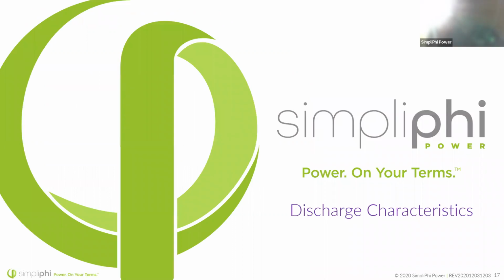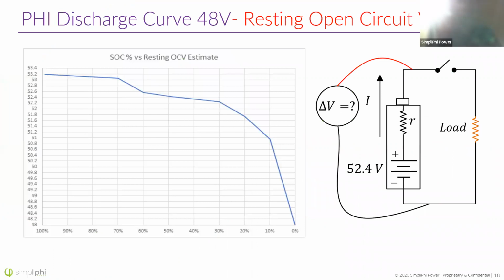Let's talk about discharge characteristics. So we just talked about the charging cycle. I told you it starts off at a constant current process, right? For our batteries, that should max out at 37.5 amps per battery. If you have 2 batteries in parallel, it would double to 75. The discharge characteristics are a little bit different, similar, but in terms of a discharging battery, our batteries are capable of surging. And so there's a little bit of a difference there in terms of discharging. So our batteries can surge for 10 minutes, and that's if you have a high output need.